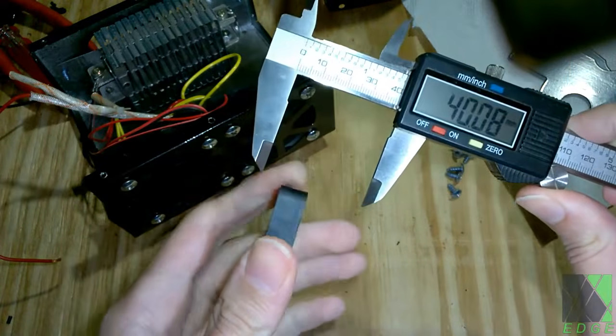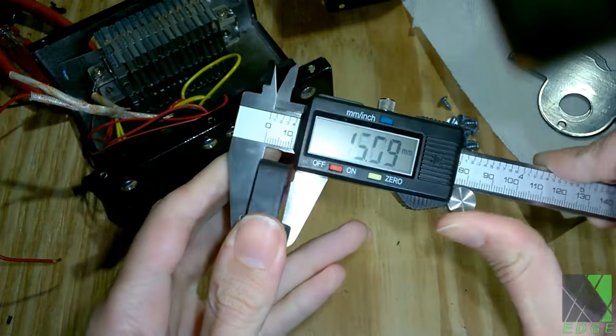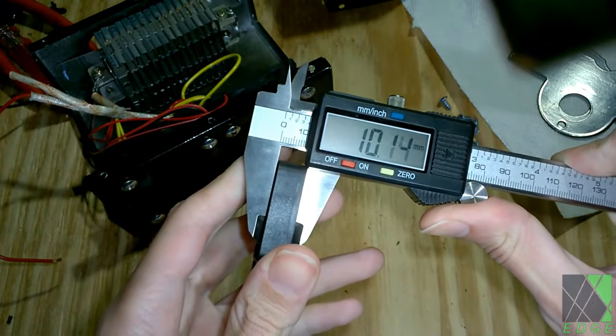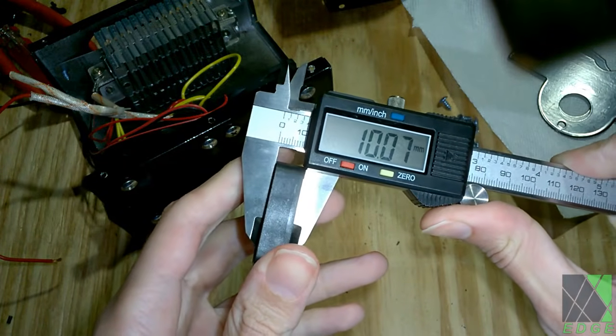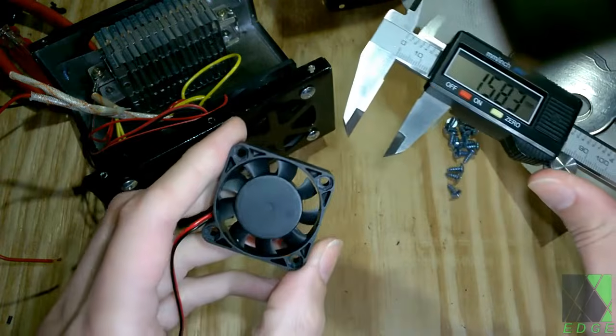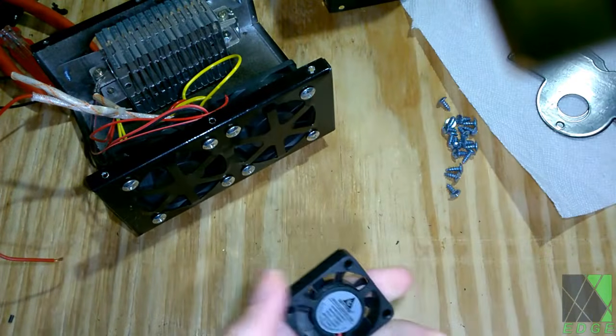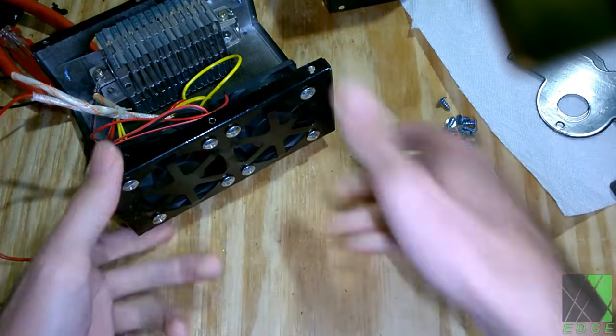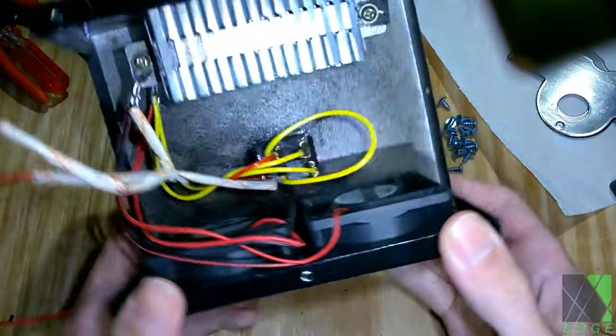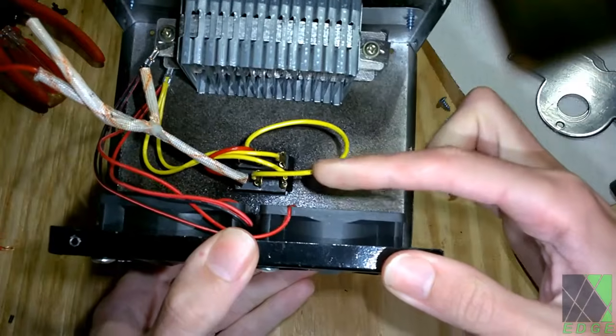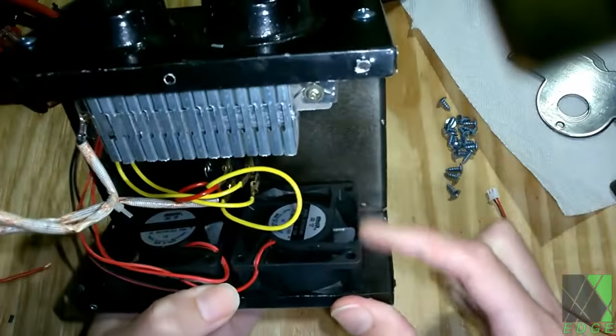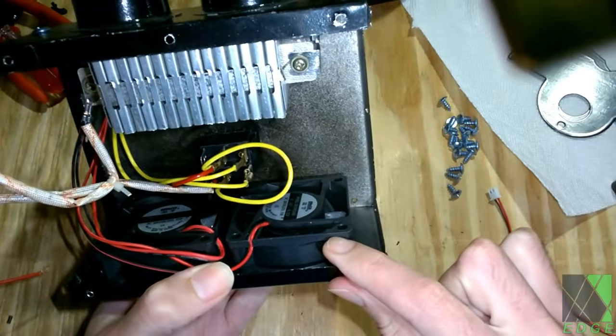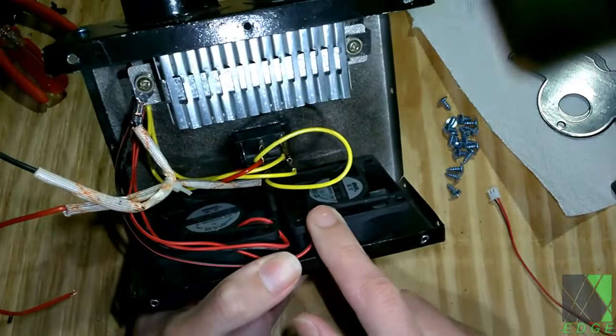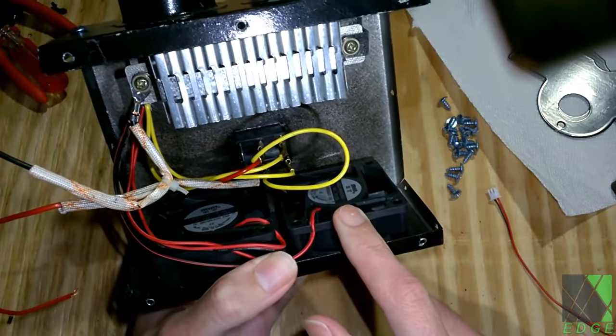In this heater cabinet, the depth doesn't matter so much, but that would be this dimension here. As you can see, this one's about 10 millimeters, so this is a 40 by 10 millimeter brushless DC fan. You would simply measure the fan that you want to replace, and you can see they can be wider or narrower, that doesn't matter, but you would need to measure from here to get the right size. I would replace these with nice high quality ball bearing fans with long life.